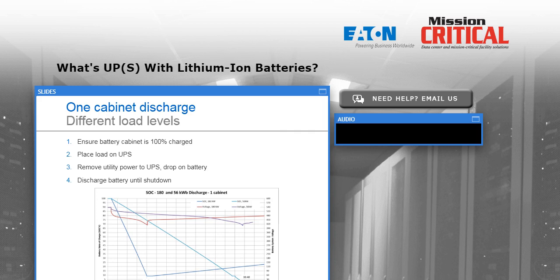Now this next slide shows an example of some of the testing that we did on one of our lithium cabinets here, and we have lots and lots of this type of information, but I won't subject you to it right at this moment. Just as an example, though, this one shows the same battery being discharged with 2 different load levels. So in one case, we start off with the battery cabinet 100% charged, load up the UPS to 180 kilowatts, and if you follow the red line here, this is the battery voltage as it discharges down to cutoff at about 9.5 minutes.